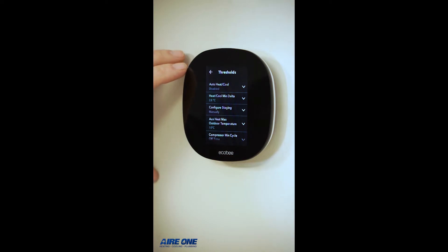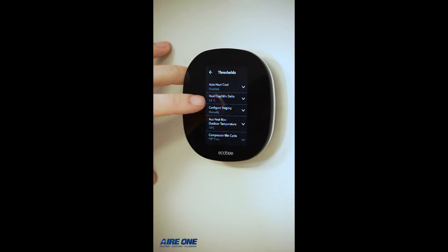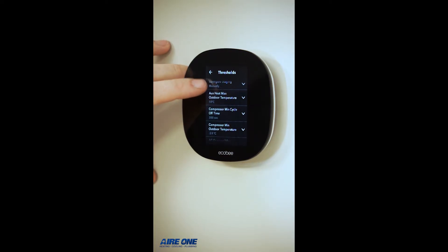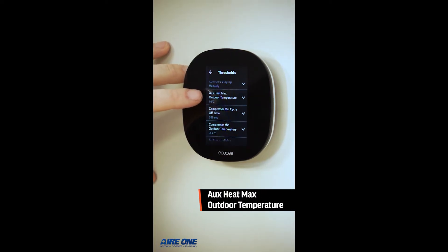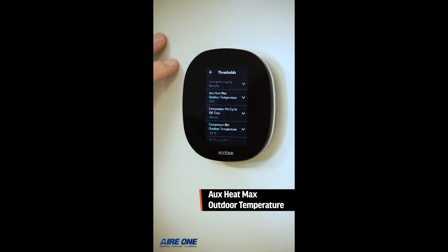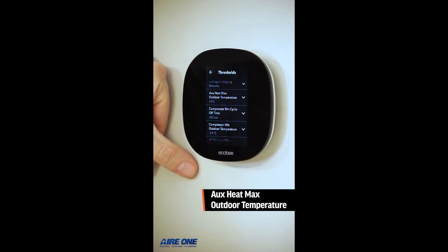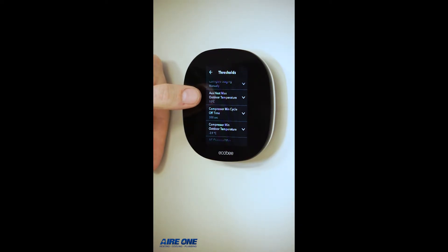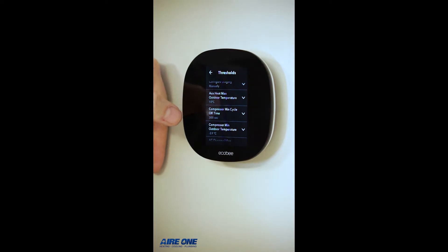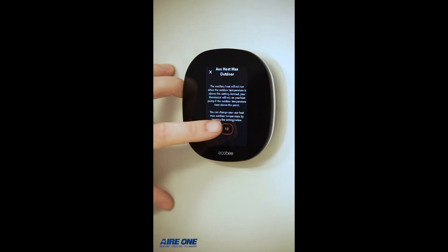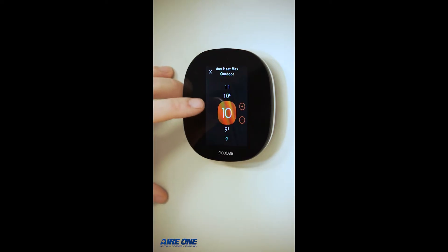Once you're in Thresholds, there are only three thresholds that you should change. The first one is the Auxiliary Heat Max Outdoor Temperature — that means your auxiliary heat, which in most cases is the gas furnace, will not run above that temperature. It is currently set to 10 degrees Celsius. Click on it to change it.